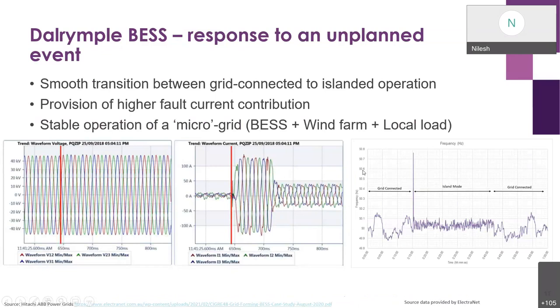Look at the response of the battery. This is the response during an unplanned islanded event. You can see the red vertical line is where the islanding has occurred. I'll try and point it out here. You can see there is a smooth transition from grid following to grid forming, or at least the formation of an island has successfully occurred. Momentarily, it has also provided a higher fault current contribution.